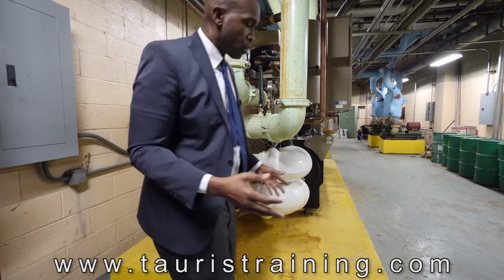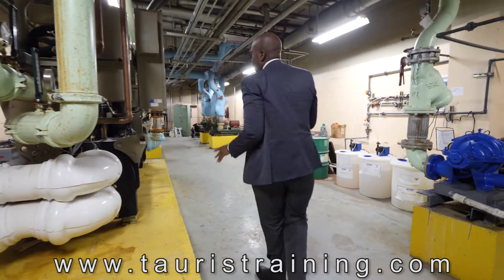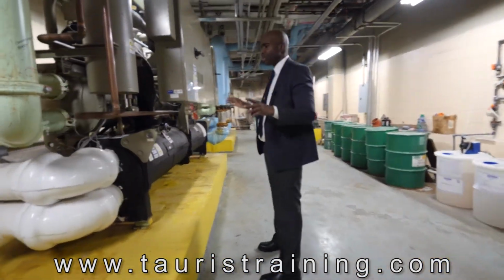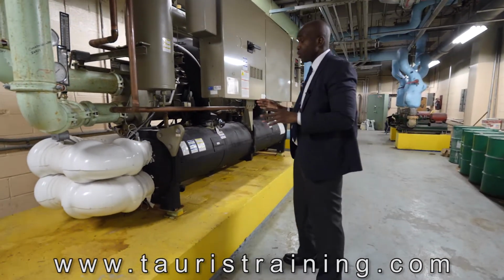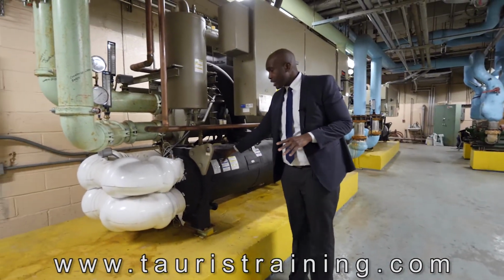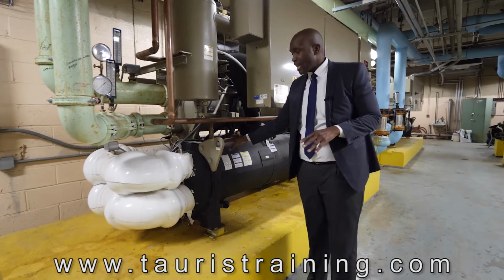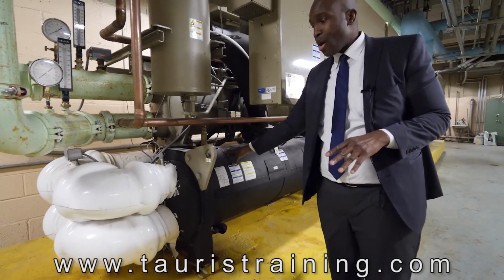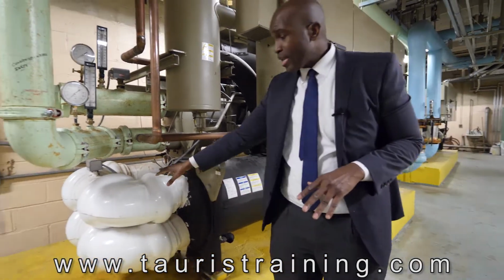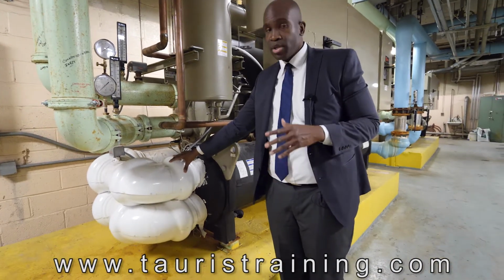So whenever we walk into a machinery room and we're trying to start identifying the components of our system, the first thing that we want to do is look out for insulation. If we have insulation, that means that it is probably going to be our evaporator. If we have insulation on our piping, then it's probably our chilled water lines.